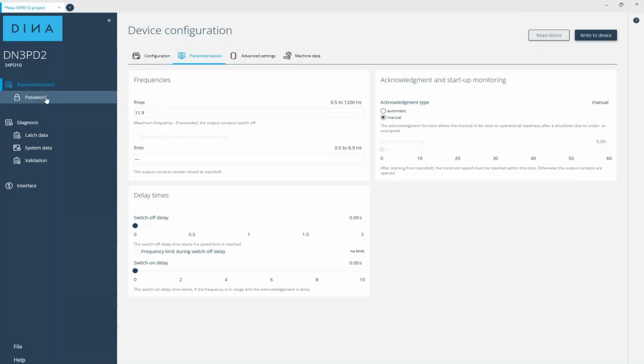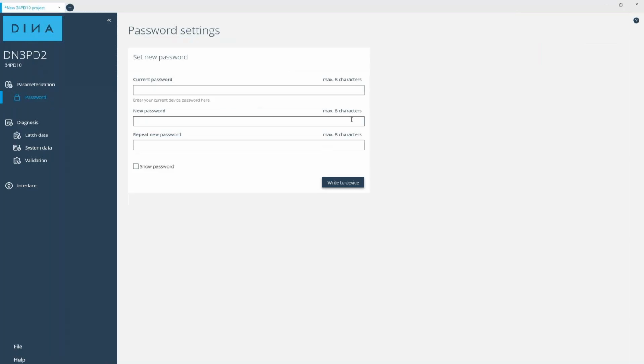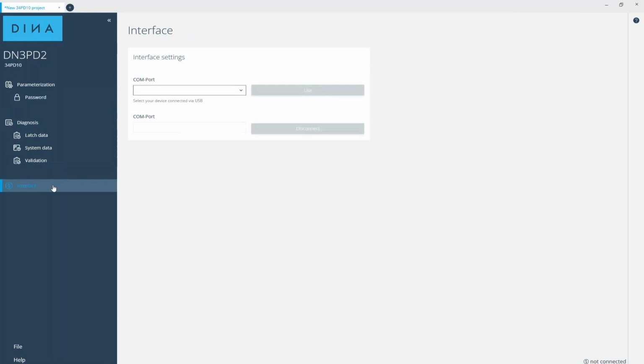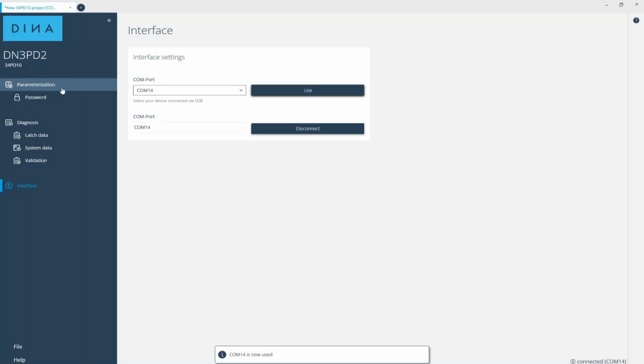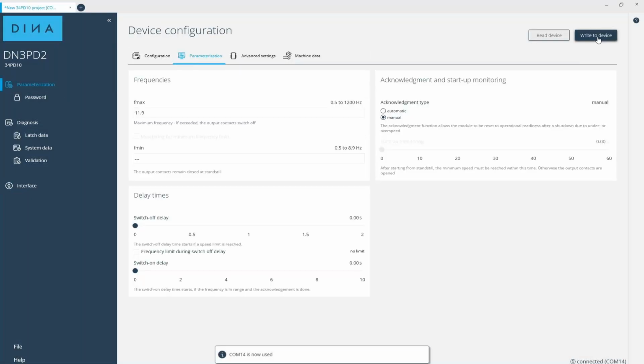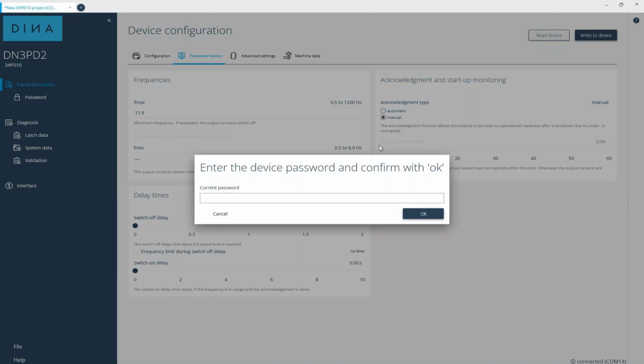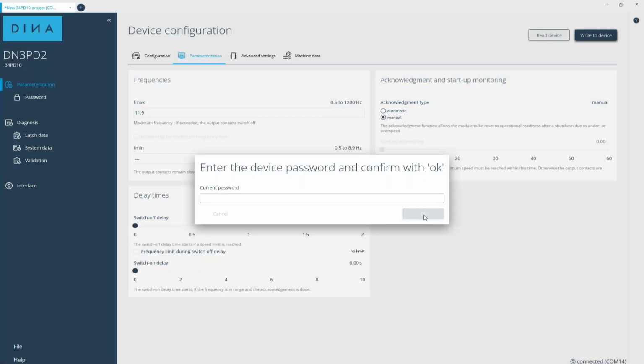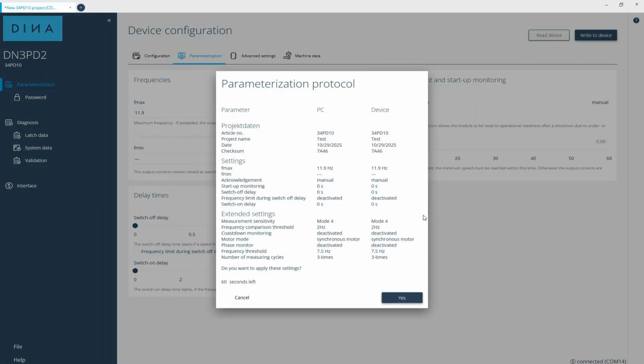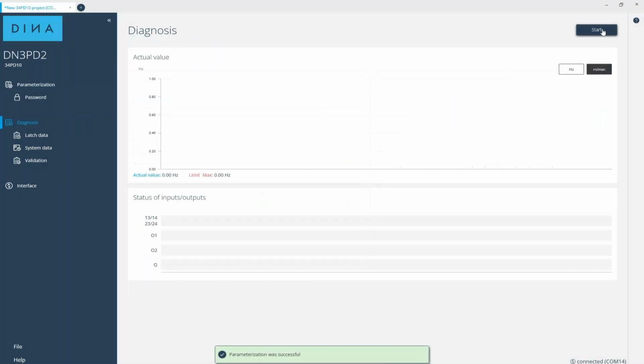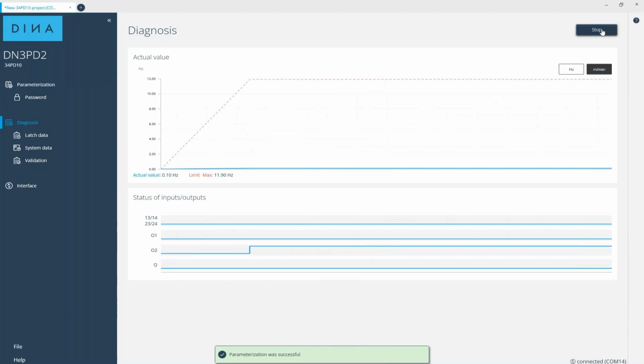We also have the option to set a password for the module to protect it against undesired or accidental changes. And to transfer the project to the module, we navigate to the interface screen and select the appropriate COM port. Once the connection is successful, we can transfer the project. By clicking Write to Device, all configured parameters are transferred. The generated parameterization protocol provides a complete documented record of all settings. It will be done automatically.